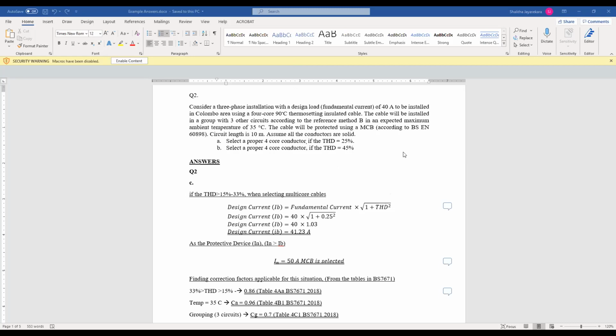What happens is in third harmonics, all the currents are in phase, so they will add up. Not only the third harmonics, all the triplen harmonics. That means third, sixth, ninth. In those triplen harmonics, your currents are in phase, so they will add up. Therefore we have to be very careful when we are doing the design. So if your THD is 25%, your neutral current is still not higher than your line current. So therefore we can easily calculate the design current using this equation.